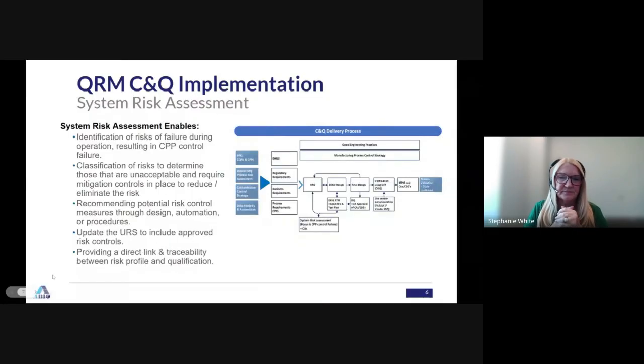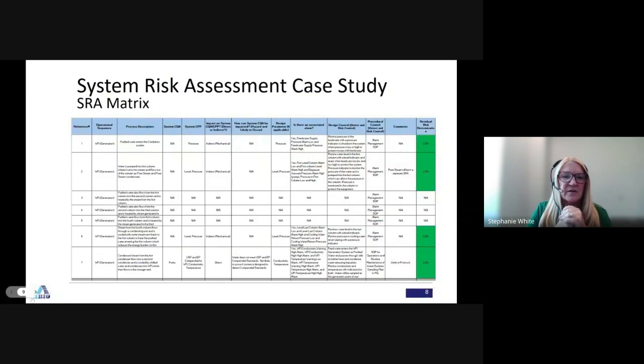And that is the requirements column, where you number them like 1 to whatever. And the next column, operational sequence, is the operational sequence or your system boundary of your system. So a WFI system, water for injection, it typically has a generation system, a storage tank, and a distribution system with it. I did this risk assessment based on all three, but just so you wouldn't have a horrible eye chart to look at, I'm just going to show you the generation.